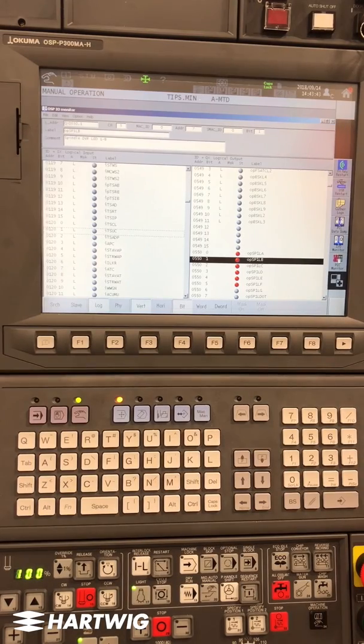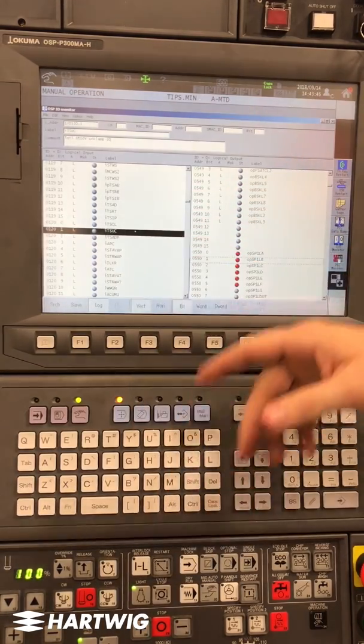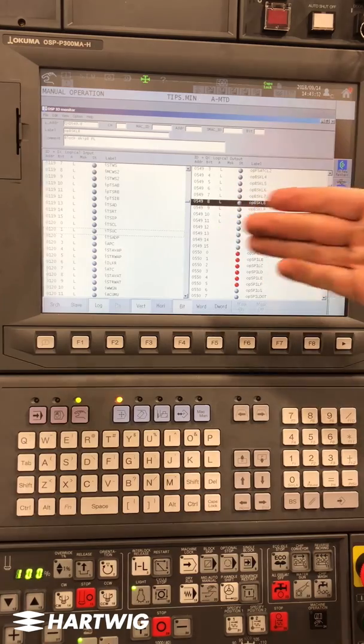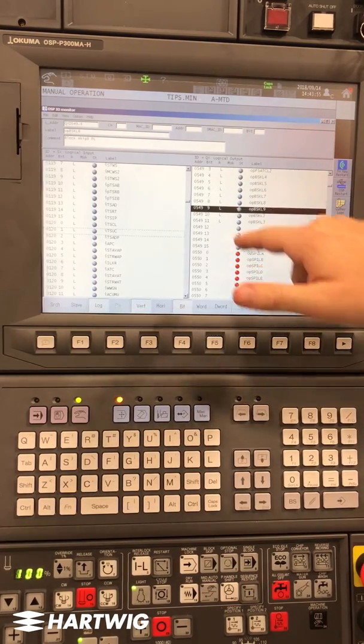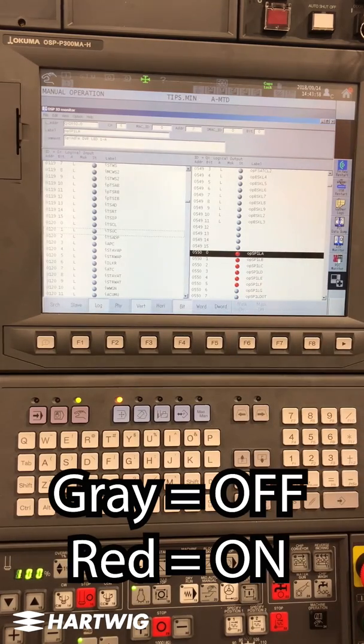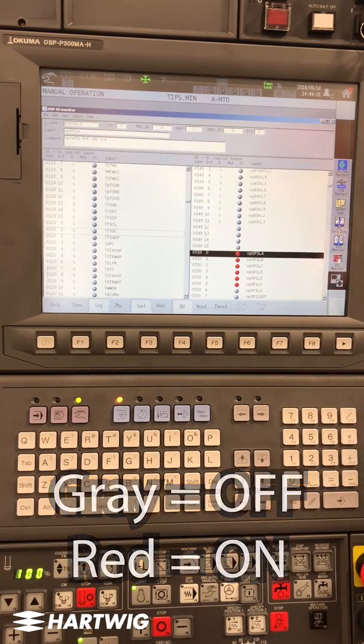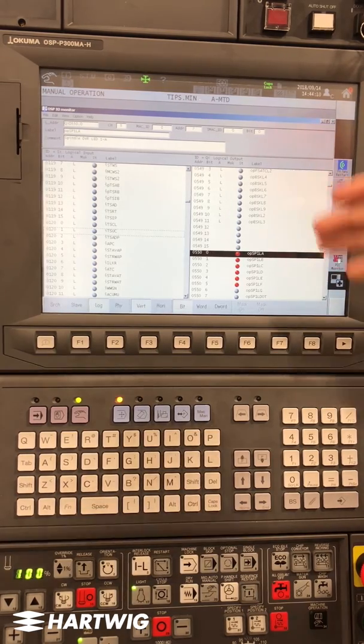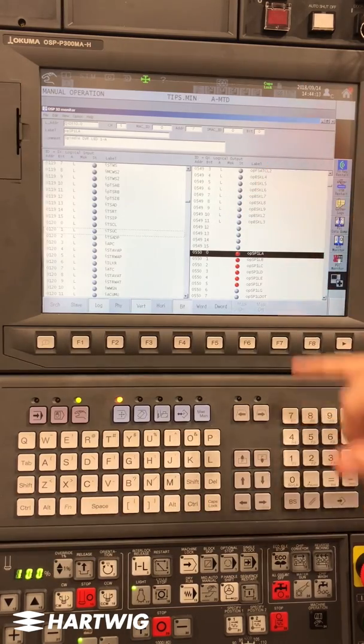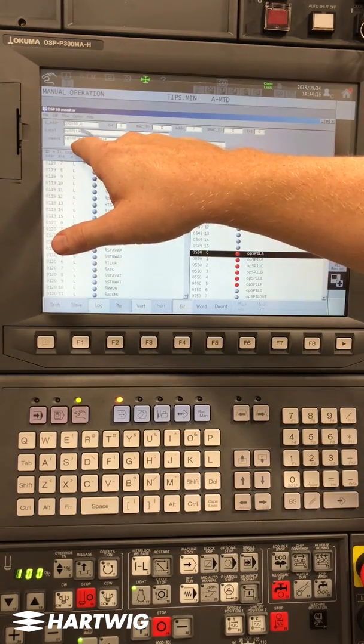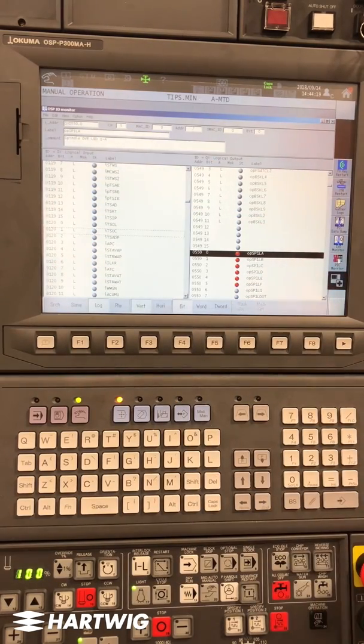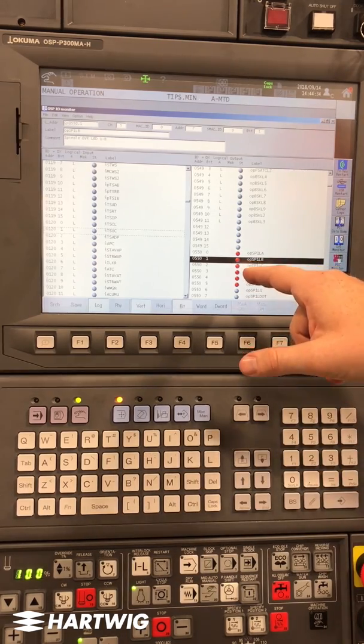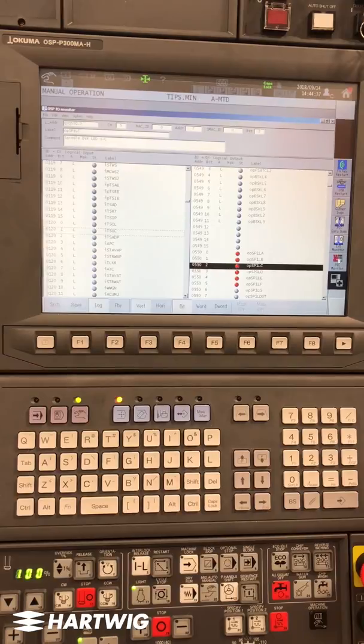What we're looking at now is a list of inputs and outputs. This list shows the current state of any given switch on a machine tool — gray representing off, red representing on. Any switch or light is going to have an on or off indicator listed in here, with a description in the top left corner as for what it is. The way we use these in a program to prevent problems is to read from the program whether that light is on or off.